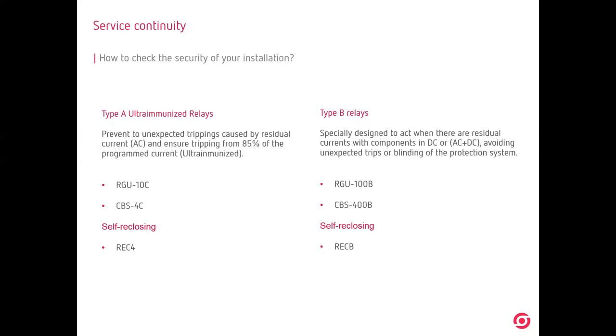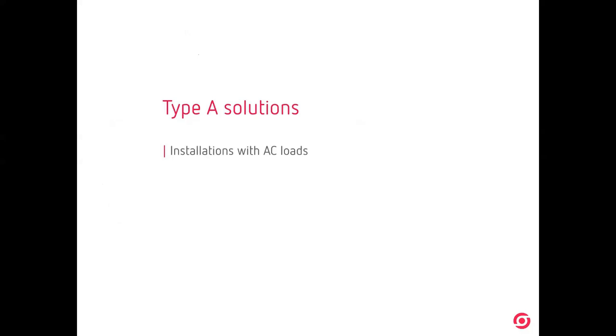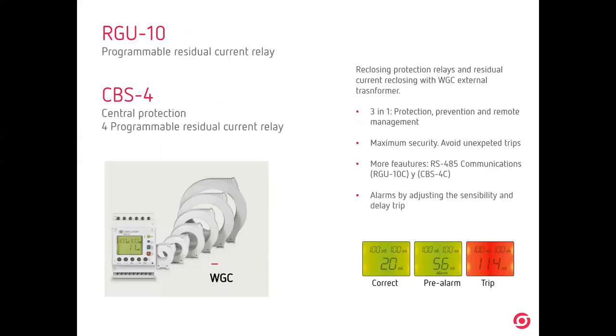Okay, which solution do we have for type A? Remember, AC loads, AC networks. We have RGU-10 and CBS4. RGU-10 is a residual current relay for one line. We have a toroidal for measuring the leakage, for one line. CBS4 is the same, but in the same three modules we are capable of reading up to four individual lines. We are measuring residual current leakage from different lines, four lines.